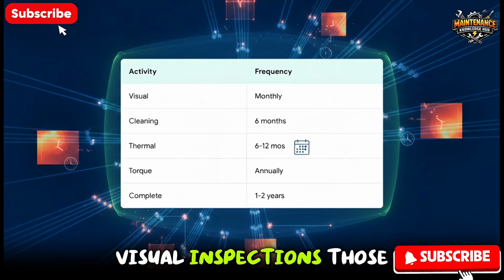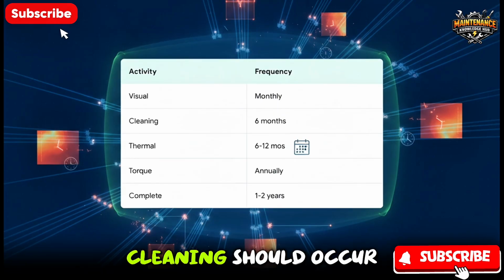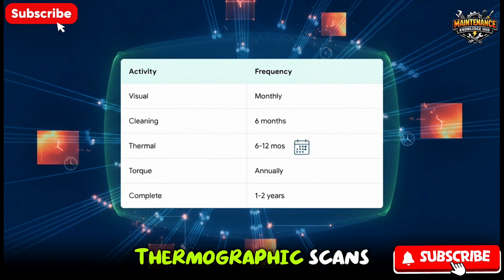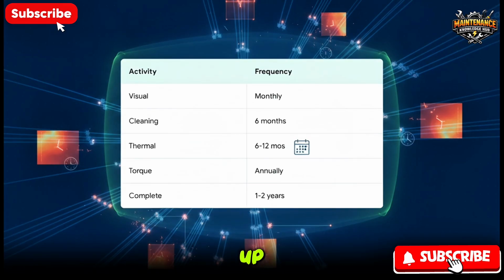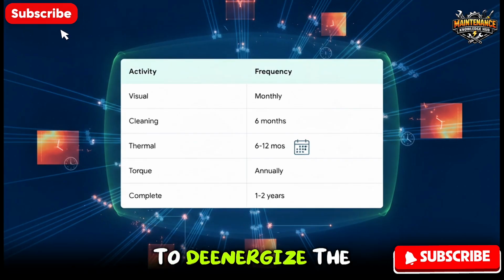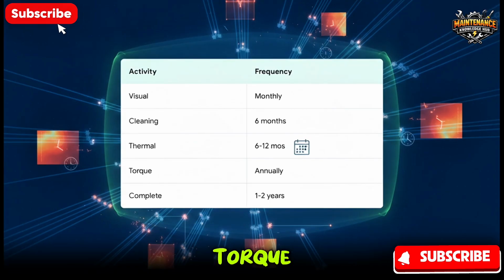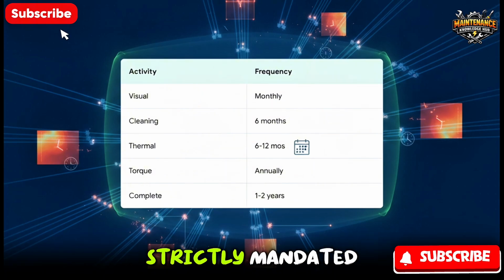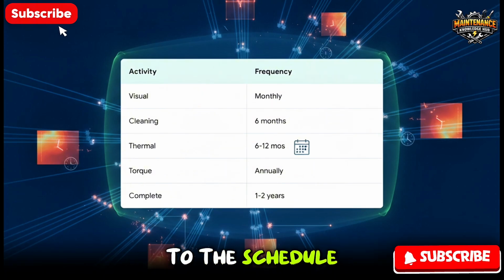To stop issues before they even start, sticking to a proactive schedule is huge. Visual inspections, those need to happen monthly. Cleaning should occur every 6 months. Thermographic scans to catch that invisible heat buildup need to be done every 6 to 12 months. Annually, you've got to de-energize the whole system to verify joint torque and perform those insulation and earthing tests. And every 1 to 2 years, a completely comprehensive inspection is strictly mandated. If you stick to the schedule, the system will easily outlive the building itself.